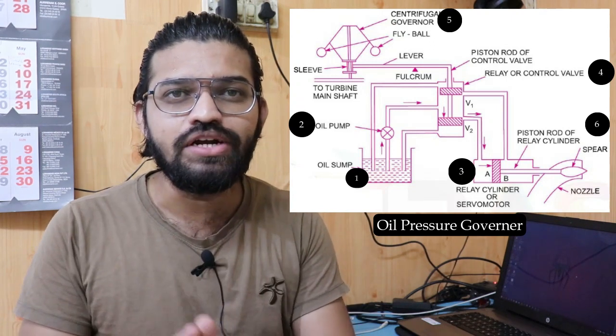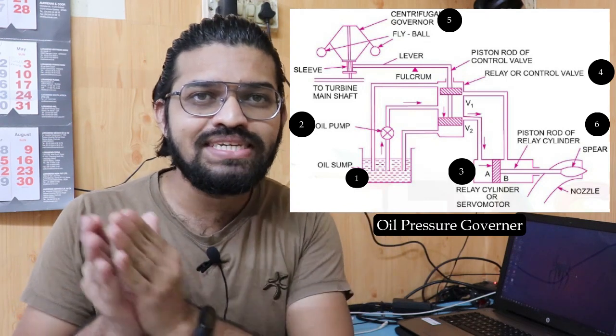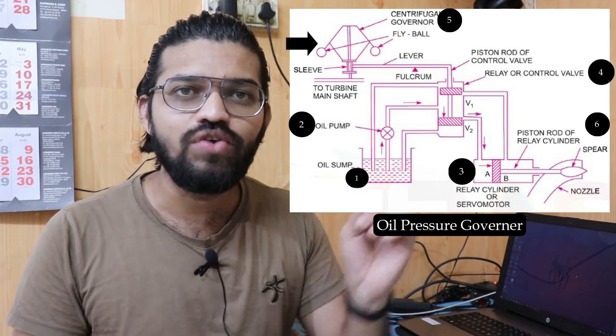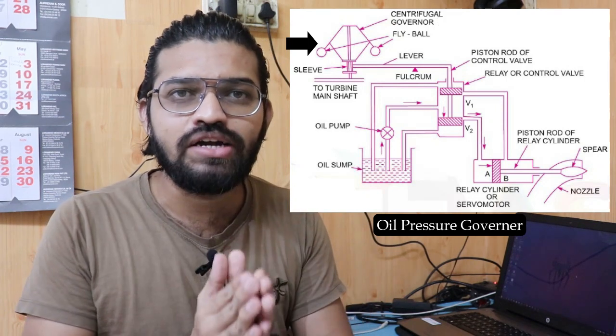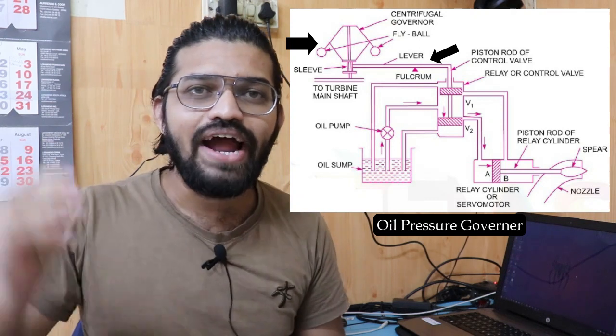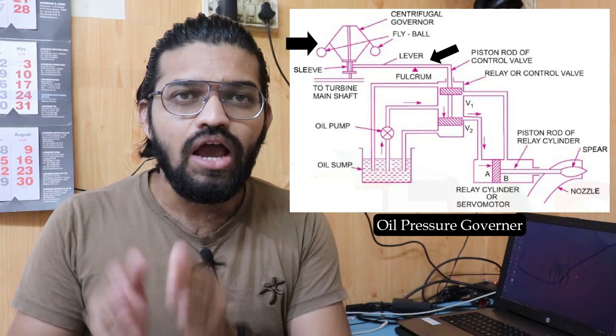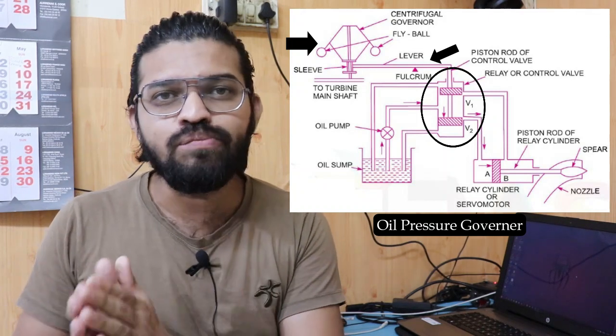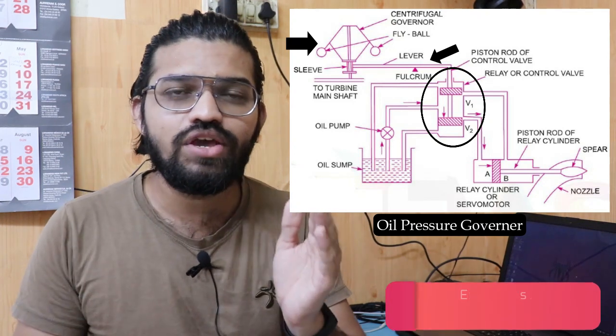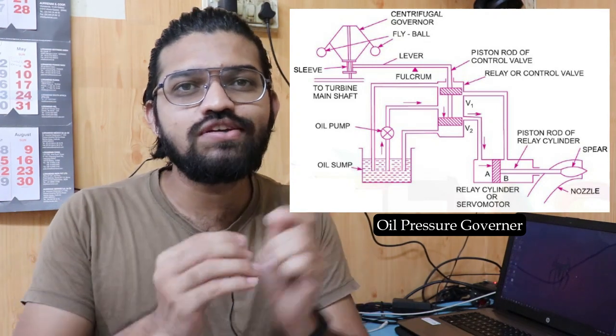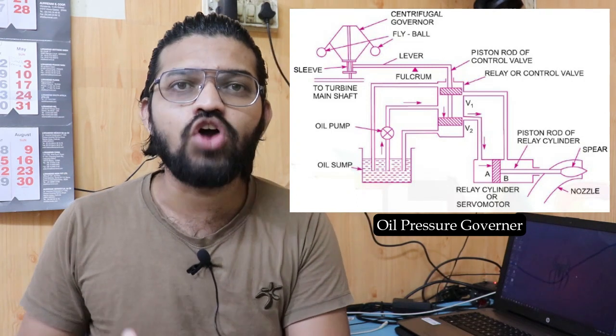When the turbine runs at constant speed, the oil pressure governor remains standstill. The governor has a centrifugal governor at the top with two balls connected to a sleeve. This sleeve is connected to a lever arm, which is pivoted at a fulcrum. The end of the lever arm is connected to the control cylinder, which has two openings V1 and V2, and two pistons that control these openings respectively.